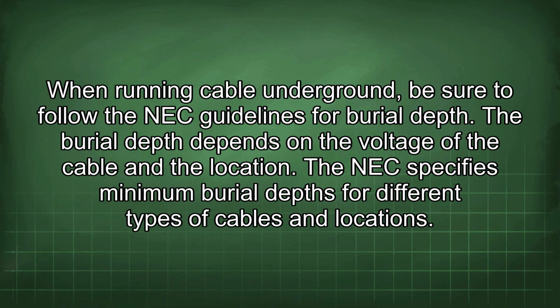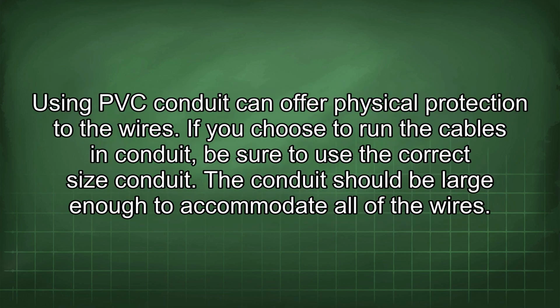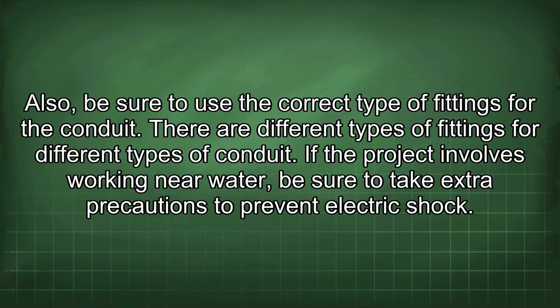When running cable underground, be sure to follow the NEC guidelines for burial depth. The burial depth depends on the voltage of the cable and the location. The NEC specifies minimum burial depths for different types of cables and locations. Using PVC conduit can offer physical protection to the wires. If you choose to run the cables in conduit, be sure to use the correct size conduit. The conduit should be large enough to accommodate all of the wires. Also, be sure to use the correct type of fittings for the conduit. There are different types of fittings for different types of conduit.